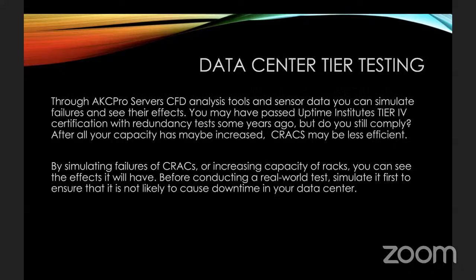You can also use this system for data center tier testing. So what I mean by that is, through the AKCPro Server, CFD Analysis tools, constrained by the sensor data, you can simulate failures. So if you are a tier 4 certified data center from Uptime Institute, then you will have had to have gone through a certification process which proves 2+N redundancy tests and so on. A lot of these tests are run, and obviously you pass them and you get your certification, but that could have been 10 years ago. Since then, you've added capacity. You've moved the CRAC somewhere else. You've added some servers. Someone's left the blanking panel out of this place. Your air filters are dirty. The CRACs are running less efficiently. Are you still able to actually meet the Uptime Institute Tier 4 certification redundancy tests 10 years after you passed them?